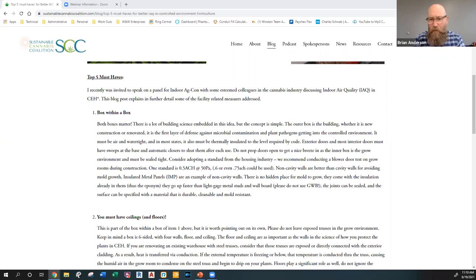And no wood anywhere, don't even use a wood plate on the floor. Use a metal plate and caulk it tightly and seam it. If you're using an epoxy floor, have that epoxy floor weld up to the side, so you have a very, very watertight, airtight inner box. That's the idea of the box within the box.